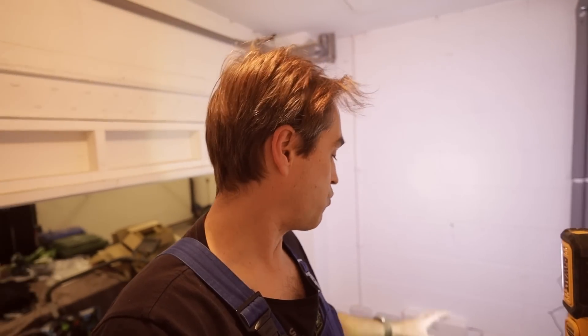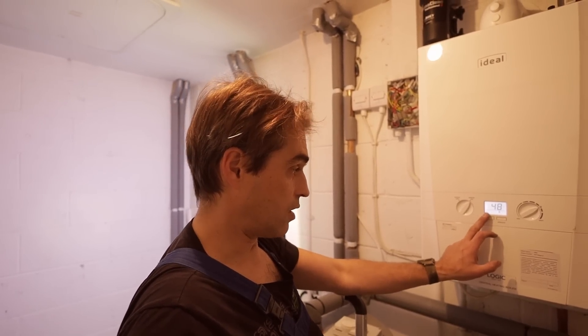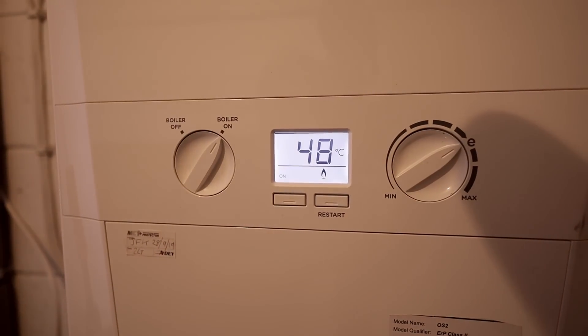I've paired all the stats with their wiring centres — got one left over because one will have to be hardwired. All the wiring centres operate independently, so when one pump comes on it's only one pump, not the whole house. You can see the boiler nicely ticking along on weather compensation — right now the flow temperature is 48 degrees.